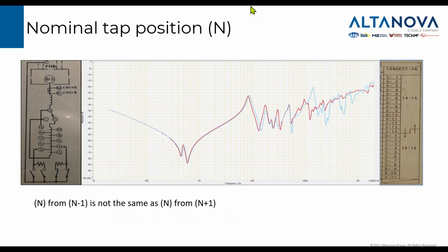When we talk about tap position, there must be one special case noted. If you consider the transformer with changeover selector, we have 2 pieces of 2 different rating plates. On one, we can see changeover selector, which selects direction in which the tap changer contacts are swept, or tap winding is actually approached.